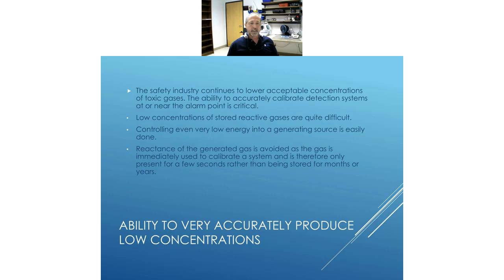So these low concentrations of stored gases are tough to get. So chlorine in a cylinder at low levels, it's just really hard to keep. The reactants of the generated gas are avoided as the gas immediately is used to calibrate. So it's generated, it comes out of a 5-foot hose, and it goes to the sensor. It doesn't get stored in a cylinder for a long time. So this is definitely the best way to get low levels and the best way to get these particular gases we're talking about today.